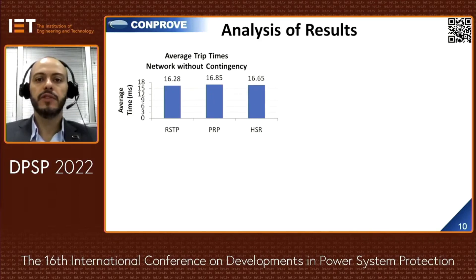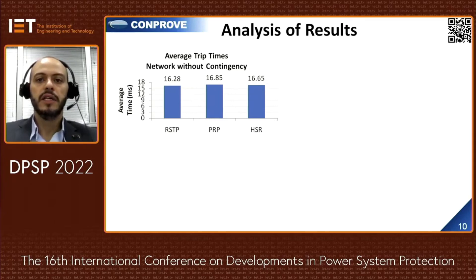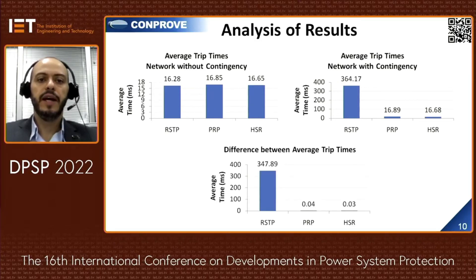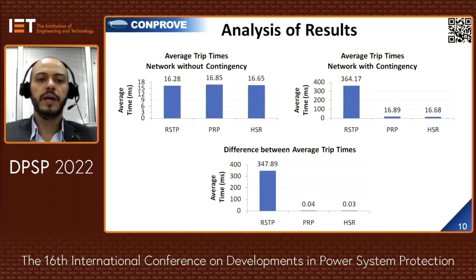The comparative graphics show the average trip times with and without contingencies, comparing the three protocols. On the horizontal axis are the three protocols: RSTP, PRP, and HSR. On the vertical axis is the average trip time. Without contingencies, the times were very close. With contingencies, the RSTP time was very discrepant compared to PRP and HSR. The time difference between network without and with contingencies is very high for RSTP and very low for PRP and HSR.